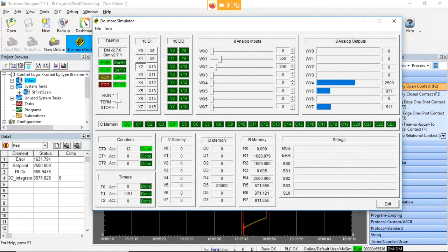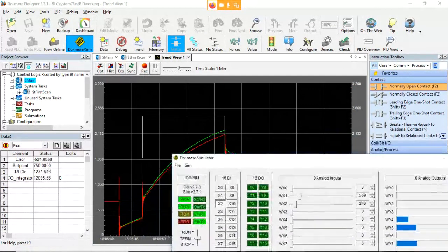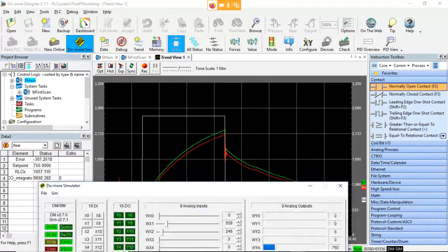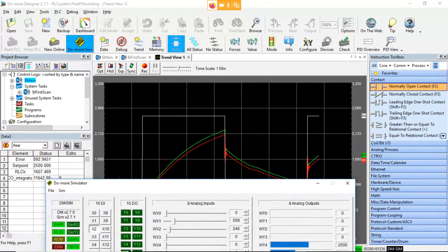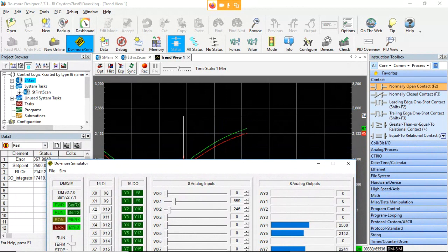Normally in the classroom, I have you flip the switch over to the left to force your integrator back to 0 sometimes, because you're integrating that error and it can get really large. Otherwise it's not going to work properly. But see how it's now driving that integrator piece. By adding the integrator, I'm getting my error much smaller. Before my error was 1,000. Now it's 600 and getting smaller by the second. The error is down to 400 now, where without the integrator the error wasn't getting anywhere near that.